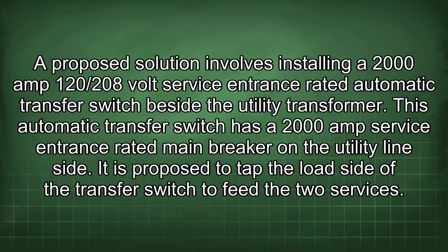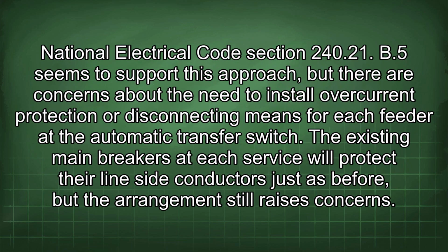A proposed solution involves installing a 2000 amp 120/208 volt service entrance rated automatic transfer switch beside the utility transformer. This automatic transfer switch has a 2000 amp service entrance rated main breaker on the utility line side. It is proposed to tap the load side of the transfer switch to feed the two services. National Electrical Code Section 240.21(B)(5) seems to support this approach, but there are concerns about the need to install overcurrent protection or disconnecting means for each feeder at the automatic transfer switch.